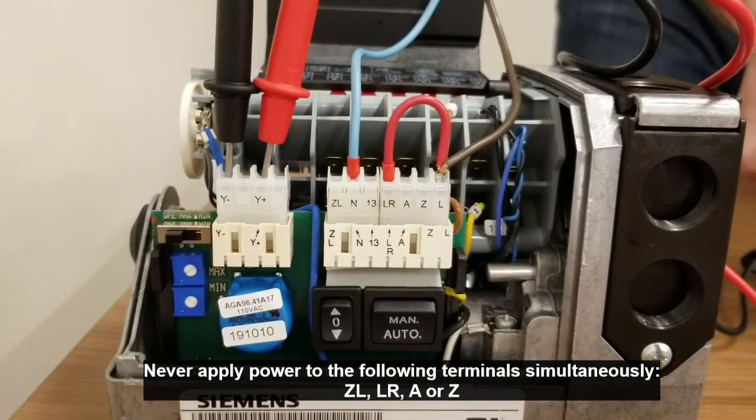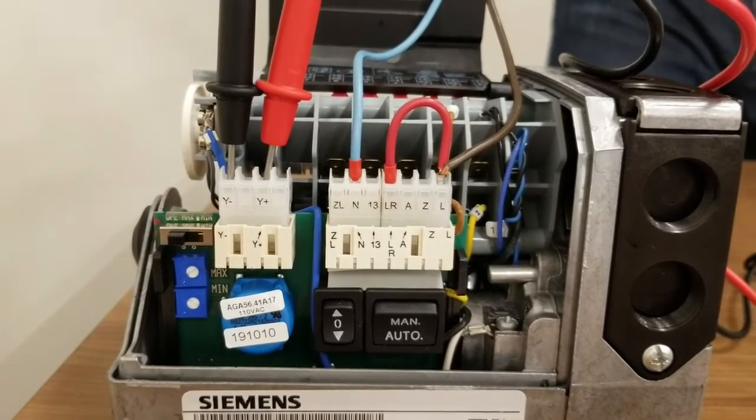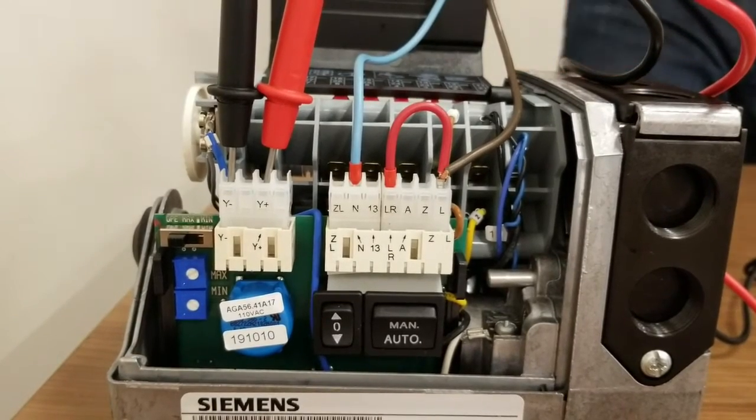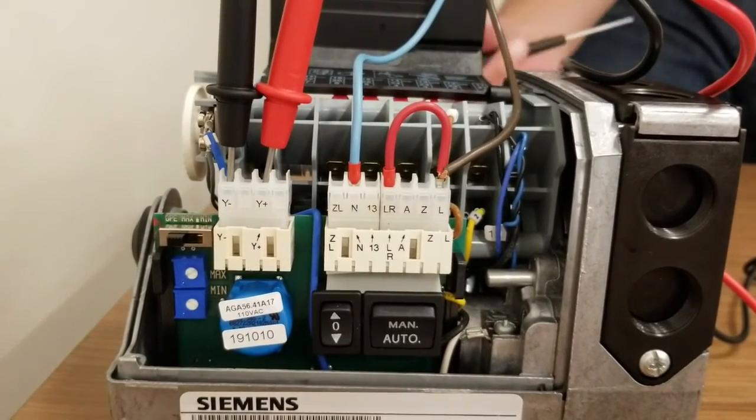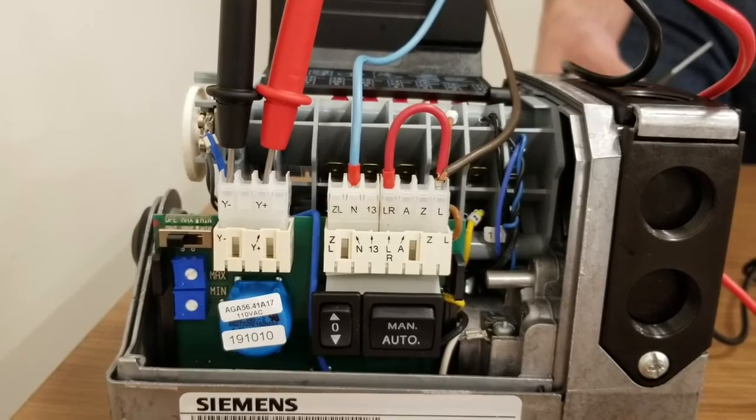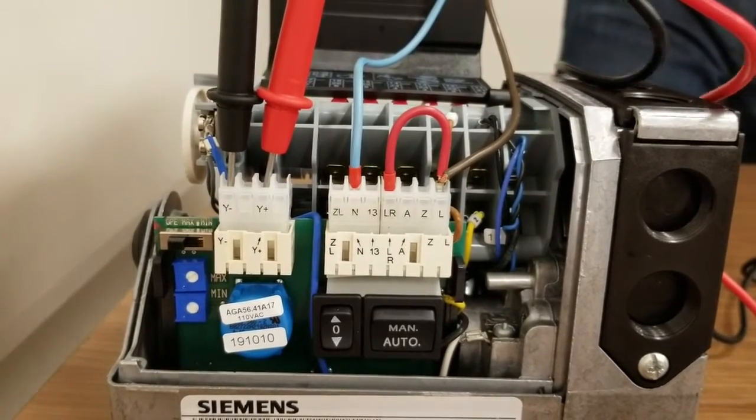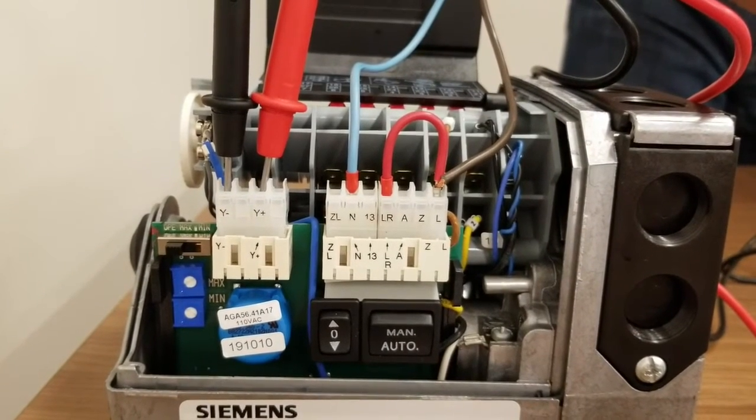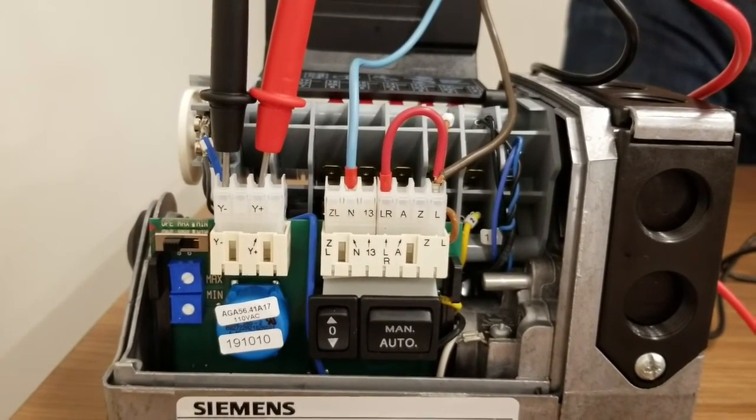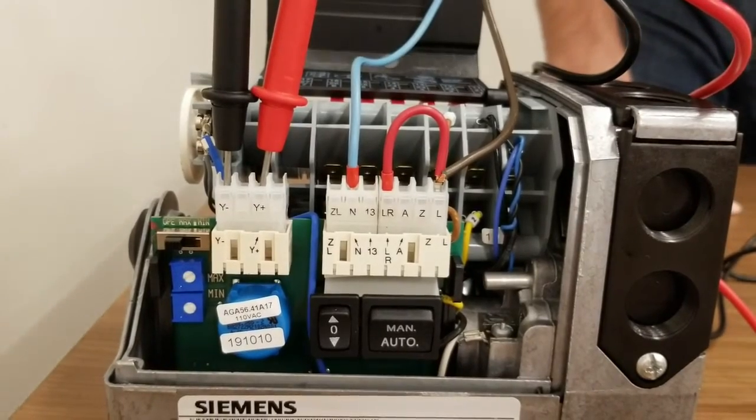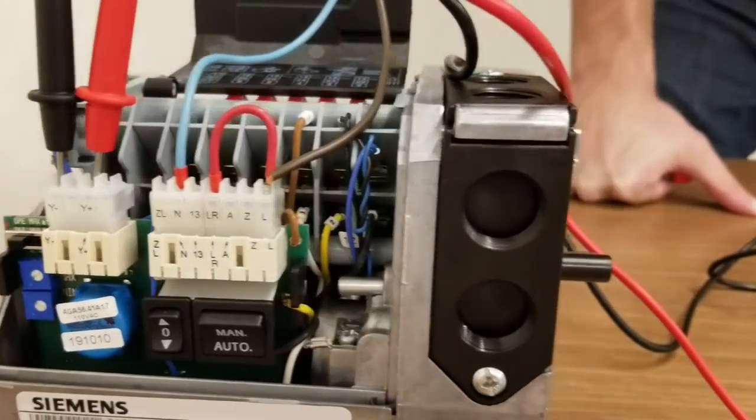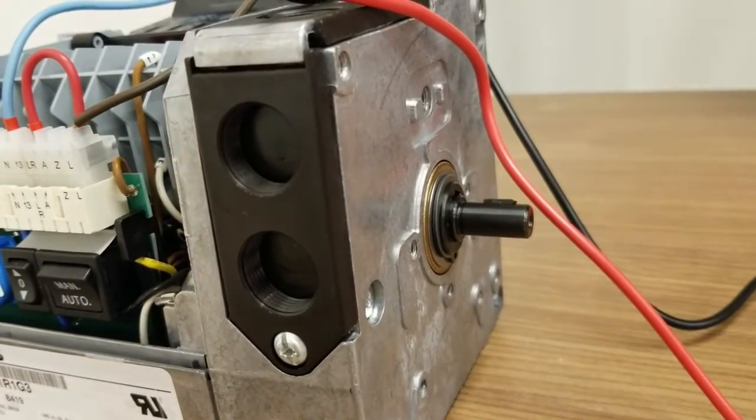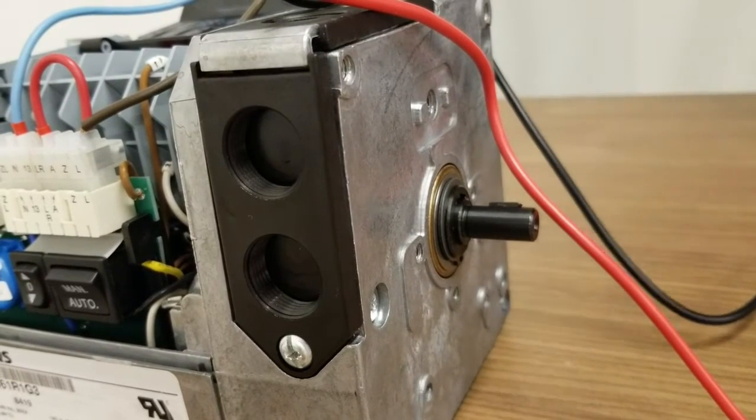Now that we have power applied to our LR, we can supply our input signal, our analog input signal, which in this case is going to be a 4 to 20 milliamp signal. I have the terminals here hooked up to a signal generator. Right now I'm going to supply 20 milliamps and the actuator is driving open. As you can see, the shaft is rotating to our open position, which is defined by CAM 1.